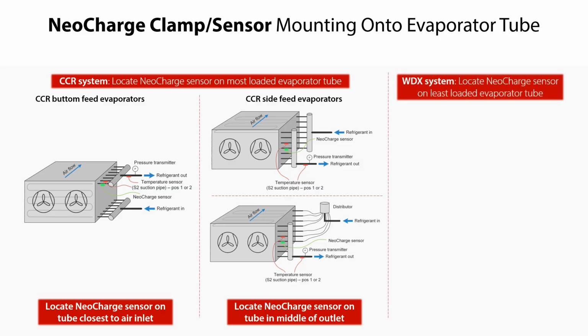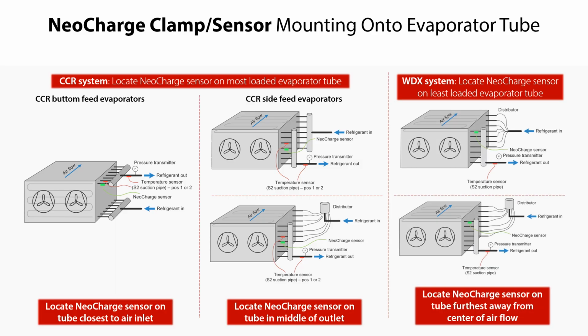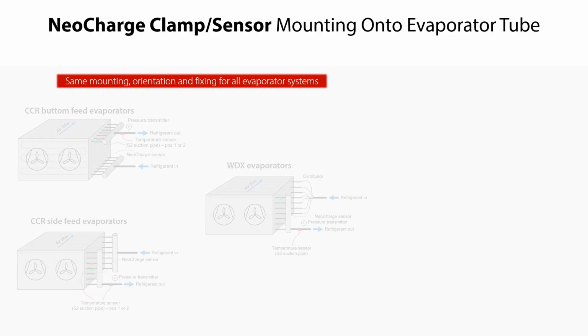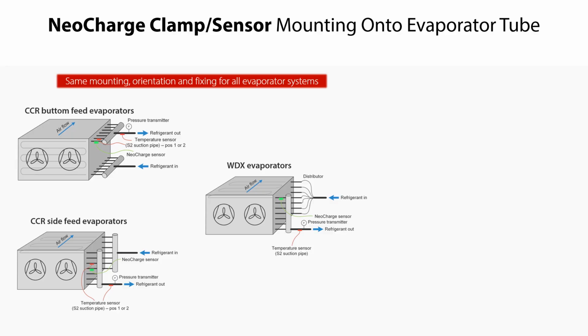For a WDX evaporator system, the Neocharge sensor should be located on the least loaded evaporator tube, meaning the tube with least gas in the outlet. This will give the least liquid in the evaporator outlet. Therefore, the best sensor location is often on the evaporator tube furthest away from the center of the airflow, as shown here, with different types of distributors included. The procedure of mounting, orienting, and fixing the Neocharge clamp with sensor onto the evaporator tube is the same for all the evaporator systems mentioned earlier.